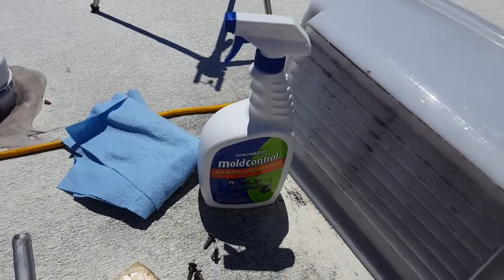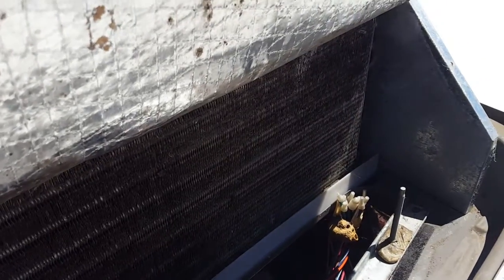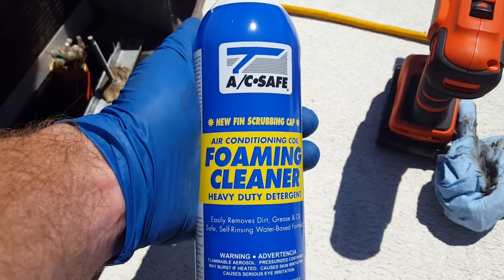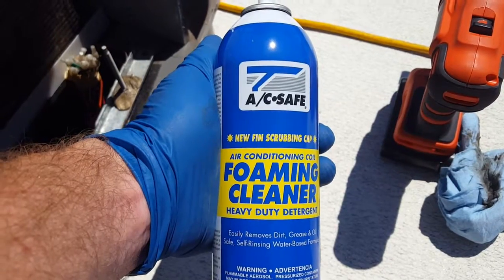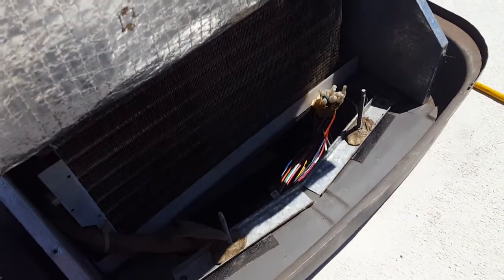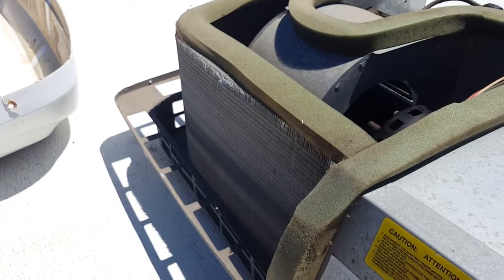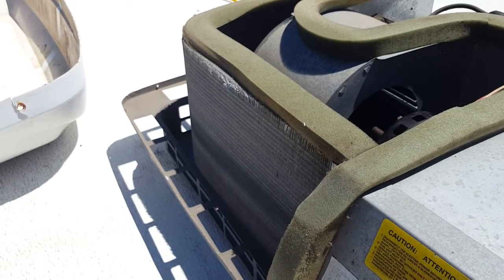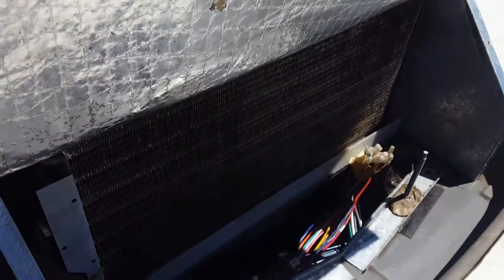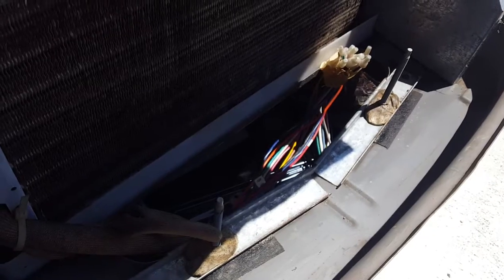I've got some good products. This one is mold control — you want to make a barrier with that. And then there's an air conditioning coil foaming cleaner. The good thing is you don't have to rinse this one — the condensation that happens in the fins will work it through. If you're cleaning your condenser fins though, you would have to rinse those because they don't produce condensation. It smells citrusy fresh too. Cover all your wires because this stuff does not play well with wires.